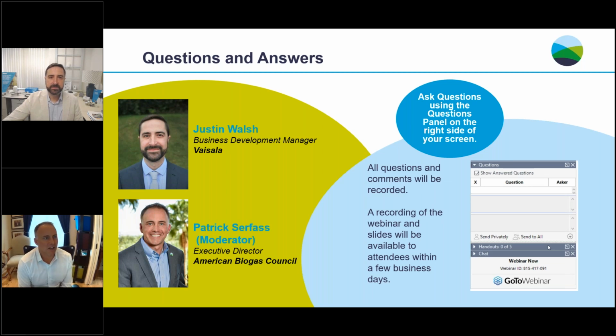Great. And I think our last question here. Can you compare the products that you offer to a typical gas chromatograph in terms of what you cover and what the gas chromatograph does? So, there's a good amount to unpack in that one, because we're not going to measure all the parameters that a gas chromatograph is going to offer. Depending on how the unit is calibrated and what type of column is in there, we can either match or exceed those accuracy specifications, or we could fall short depending on what part of the process they're measuring.